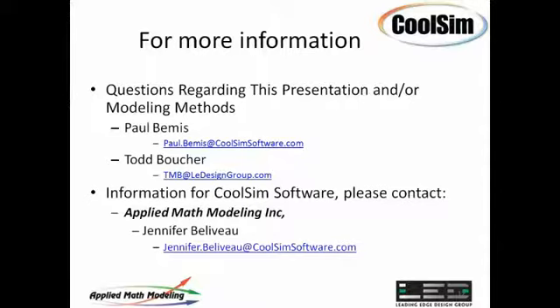The harder part is getting the cold air over to where you want it to be so you can cool the IT equipment that's hot. Oftentimes you have enough cooling capacity on paper, but what you don't know until you run an analysis like this, like we've done with CoolSim, is can the cool air get to where it needs to go under the condition where these are on and these are off. So having studies where you can turn them on and off and run them concurrently to understand the dynamics under the failure modes is an important component of overall data center design.